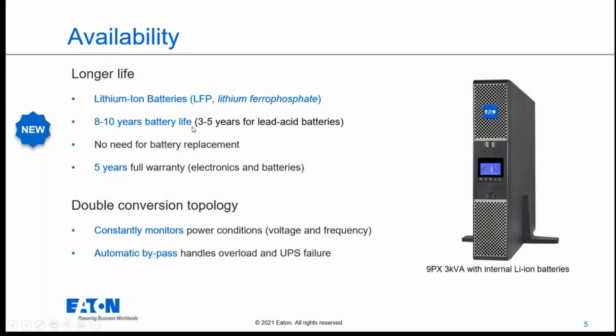We are using lithium-ion batteries as explained, so the technology is LFP, lithium ferrophosphate, if you need more details. The expected life of these batteries is 8 to 10 years. Remember, for lead acid it's 3 to 5 years, so usually with lead acid we recommend replacing the battery after 4 years. Here, the batteries will last 8 to 10 years, which is the typical life of a UPS up to 3 kVA.